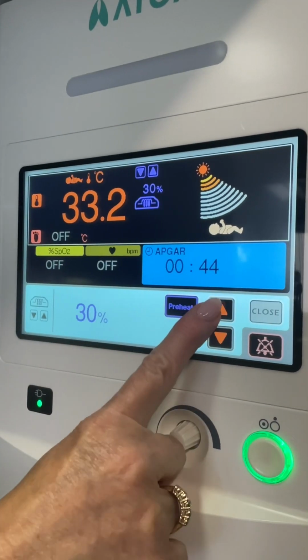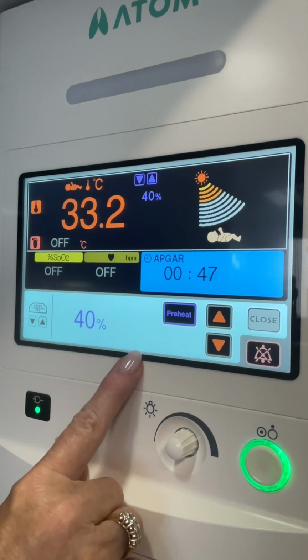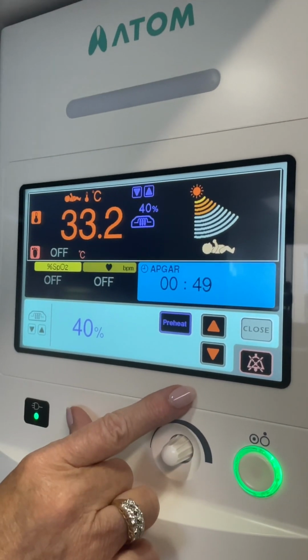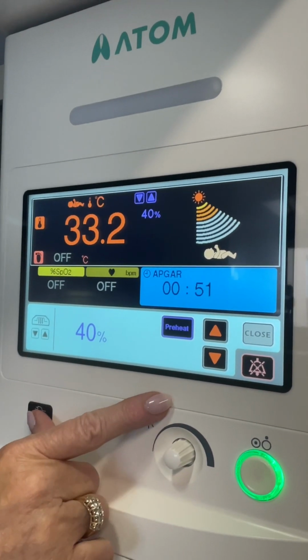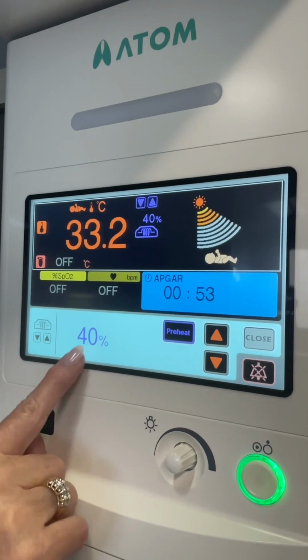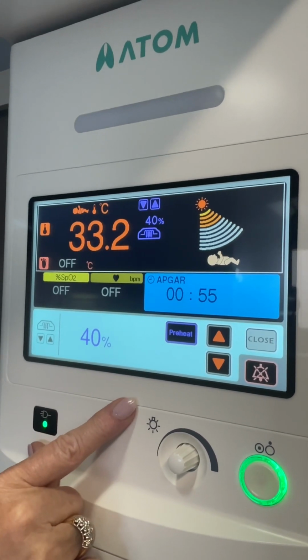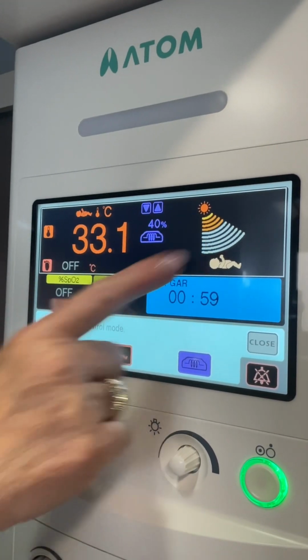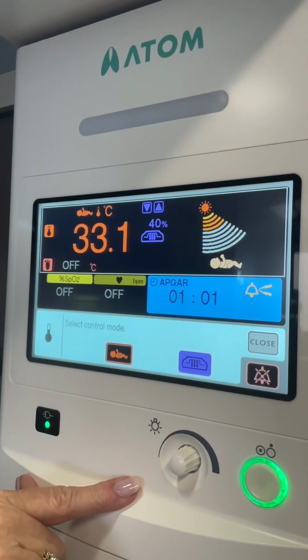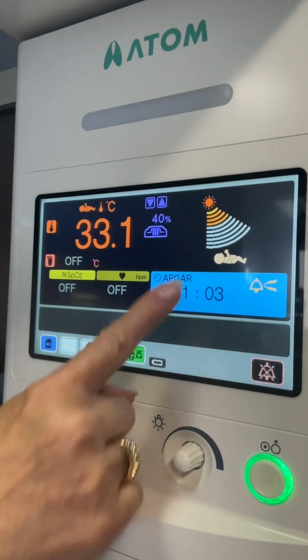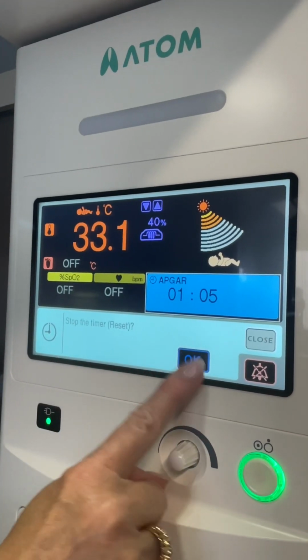This is your manual mode, which is a percentage of heat. So 25, 35, 45% heat. It's a 500 watt heater head. With this, remember any heat over 30%, so 35 to 100%, every 15 minutes, you will get a check baby alarm. It will turn the heat to 0. 1 minute APGAR, by the way. To turn APGAR off, just touch it. It'll say, do you want to stop and reset it?